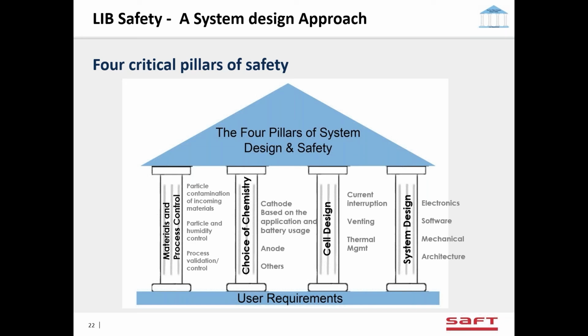We've talked about the choice of chemistries and how that can affect safety. For Flexion, we choose iron phosphate. We talked about cell design. It's not just cylindrical and module design, but also how you handle venting. In our cells, we provide a current interruption device, which, if the cell vents, the pressure in the cell opens the circuit so that it takes that cell out of the current path, and that stops any more current from flowing in that cabinet.